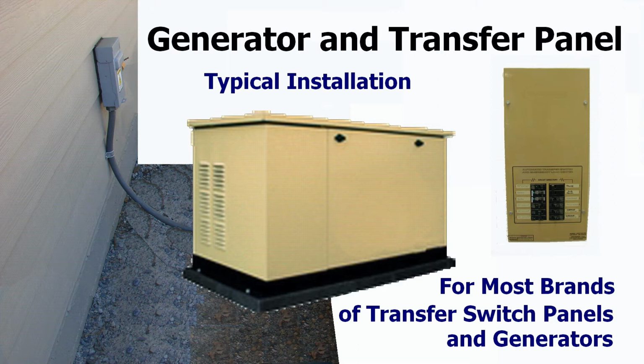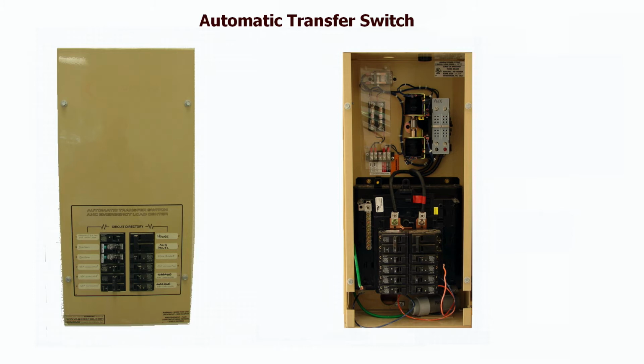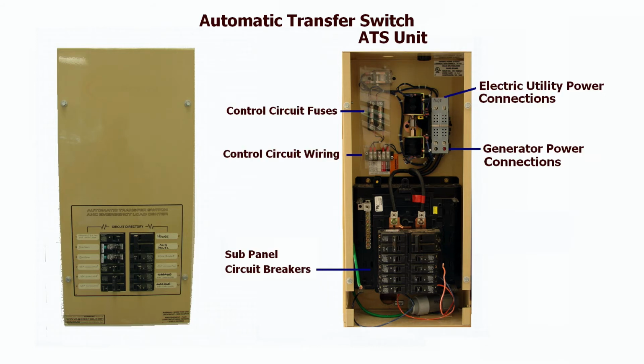This installation will be covering installation of the generator and the transfer switch, which is pretty much typical for most brands of transfer switches and generators. We're going to be looking at the transfer switch itself, starting with what it does. This is an automatic transfer switch. It transfers and activates automatically when the power is lost from the utility. It switches over to the generator power after the generator has been turned on, and then it transfers the power over to the panel of the generator.